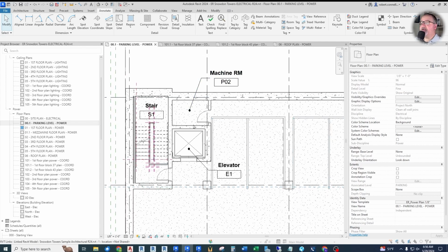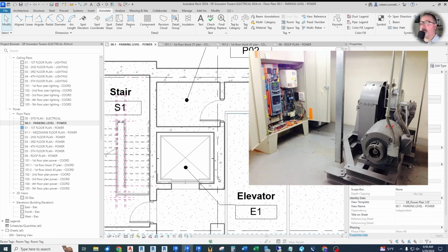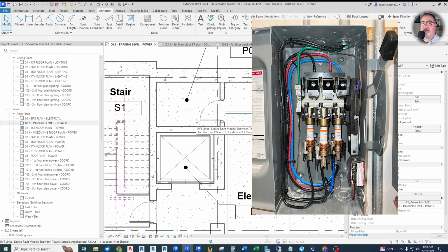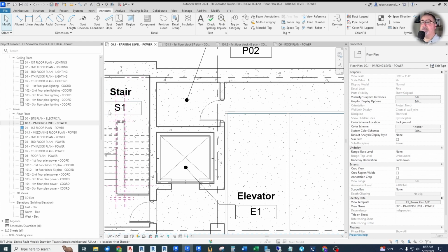When you have a separate machine room like this, they're going to have a three-phase feed to the elevator motor, whether it's a hydraulic pump for a hydraulic elevator or a traction elevator with a three-phase motor. But there's one big disconnect, usually a fused disconnect, feeding this elevator. So I'm going to show that with a motor connection.